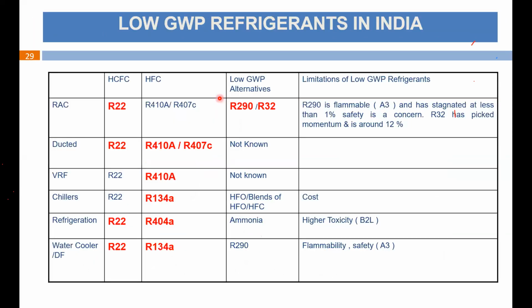So what are the low GWP refrigerants now available in the Indian context? Till now we have talked a lot about the global context, global refrigeration, and global alternate refrigerants. Now, what about India? For RAC, room air conditioners, we are still using R22, and HFC refrigerants are also being used. Some of the cases are R410A and R407C, and the low GWP options are R290 and R32.